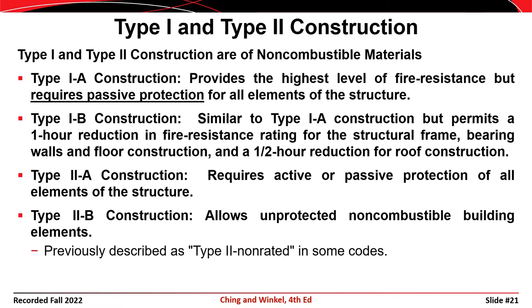As you move from Type 1A to Type 2B, the requirements for fire resistance are reduced, but the susceptibility to fire is increased. Thus, if you look at IBC Table 504.3, you'll see that as you move from Type 1A to Type 2B, the height restrictions on the structure become more significant.